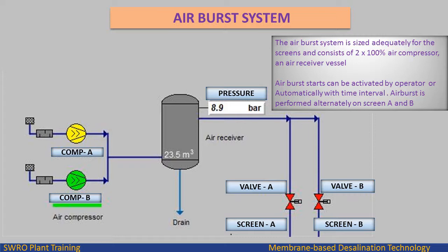The air burst system is sized adequately for the screens and consists of 2×100% air compressors and an air receiver vessel. Air burst starts can be activated by the operator or automatically at set time intervals. Air bursts are performed alternately on screens A and B.